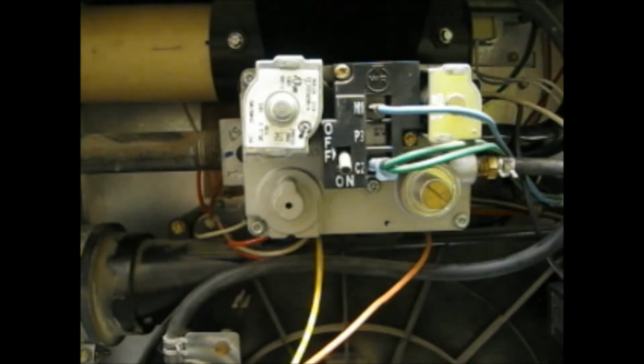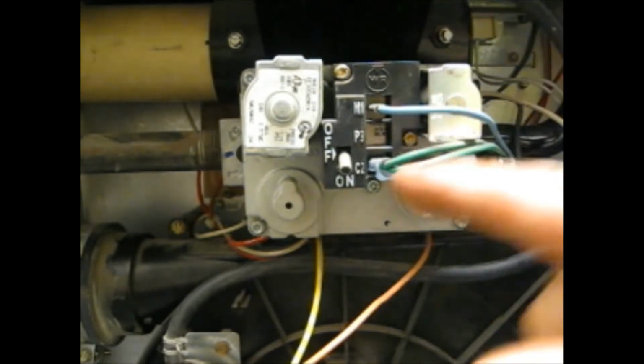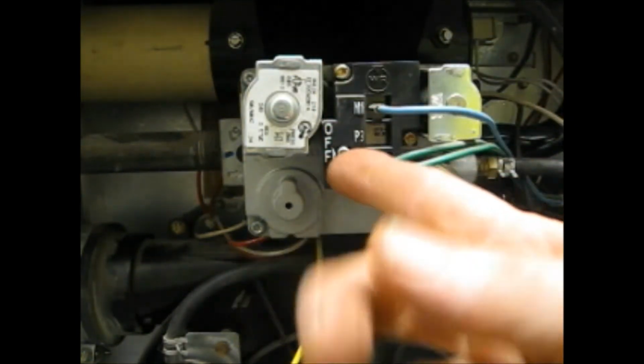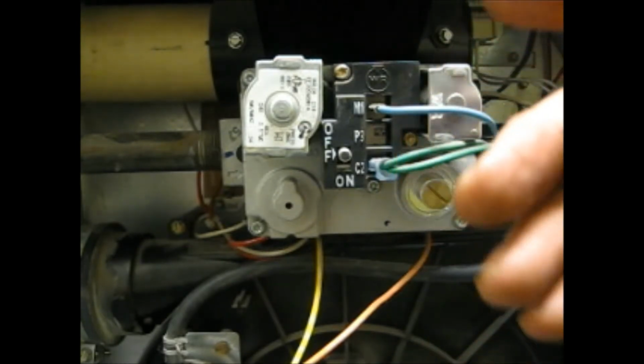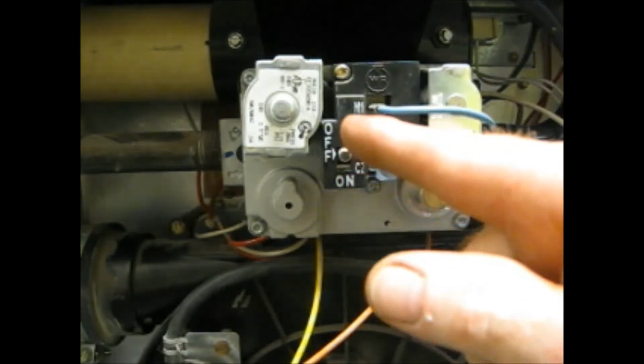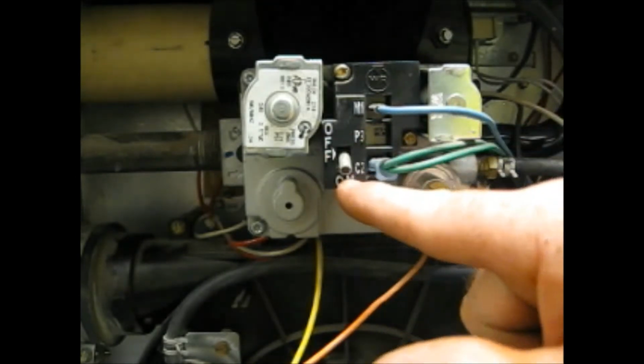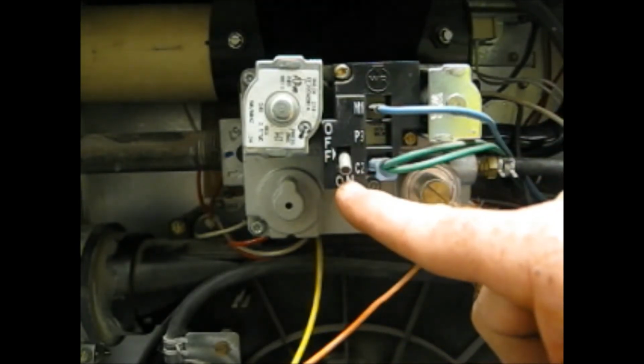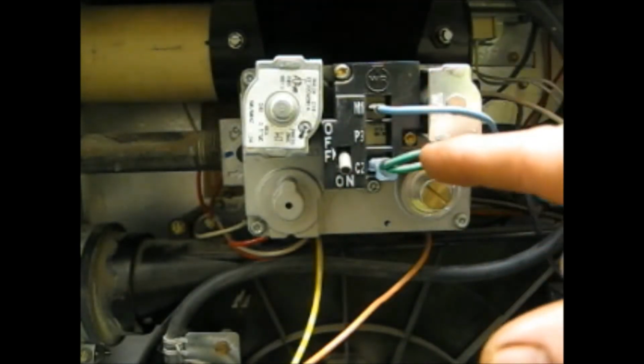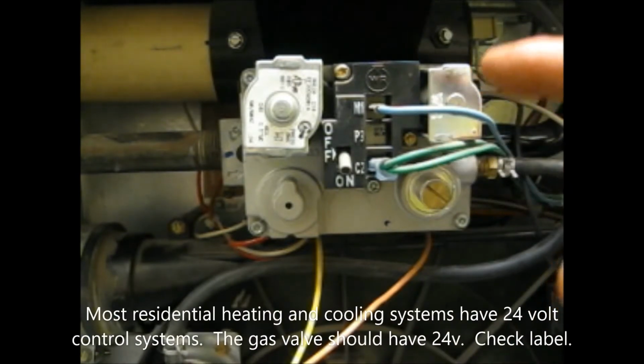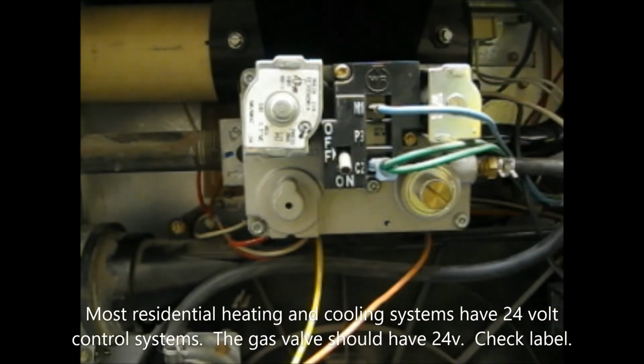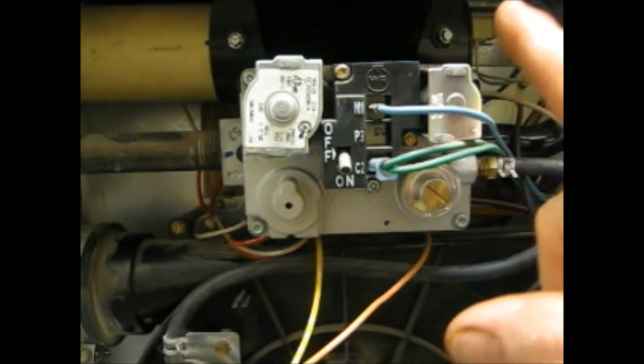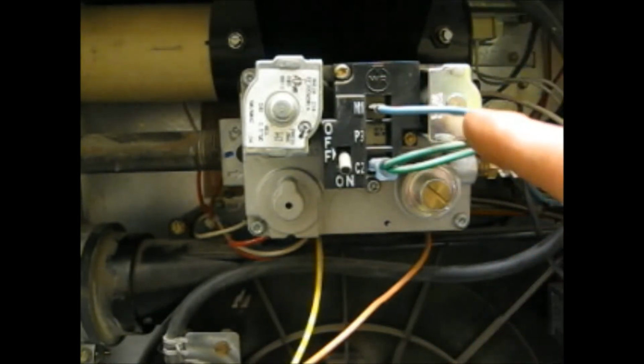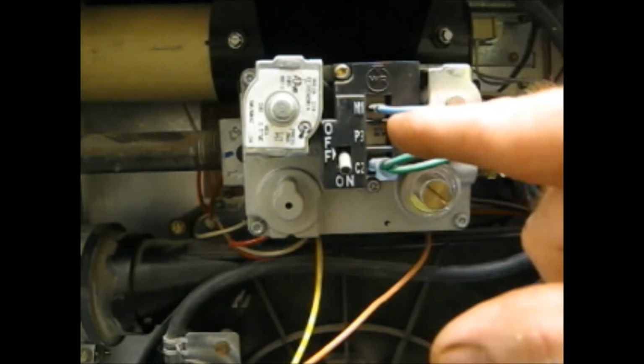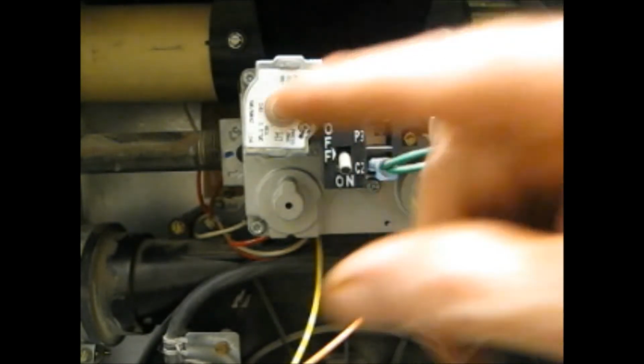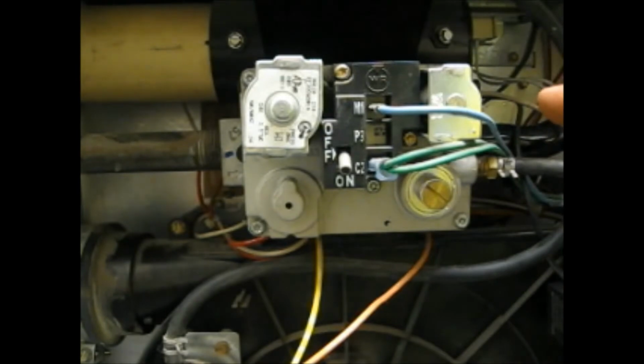Now we can do the same thing with the gas valve. Now just to note, there is an off-on switch on this gas valve. I can't think of any reason why someone would flip this off, but it should be in the on position. So what we're going to do, we're going to do the same thing we did with the hot surface igniter. The next step in the sequence is once the hot surface igniter gets hot, a signal will be sent to the gas valve to open up and to let the gas start to flow up to your burners.